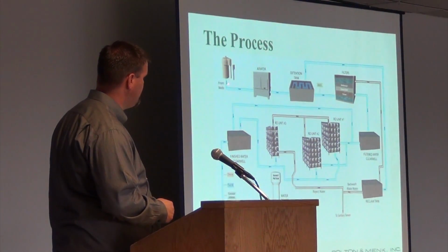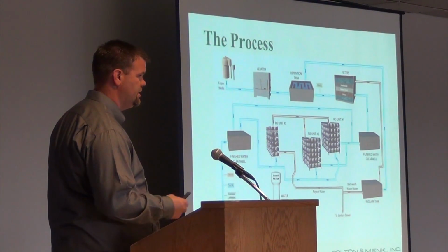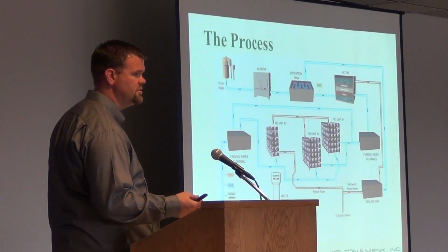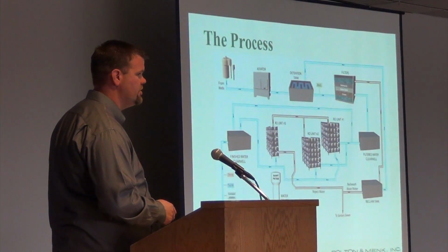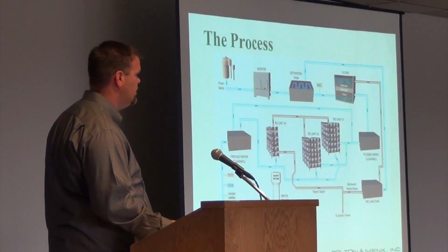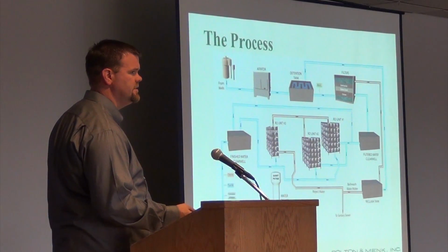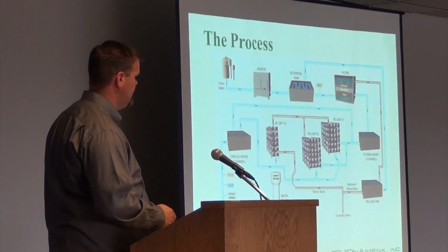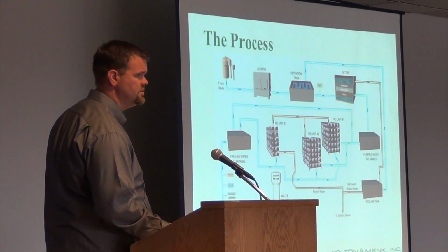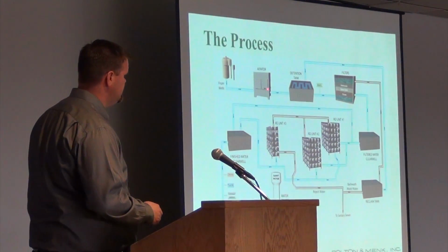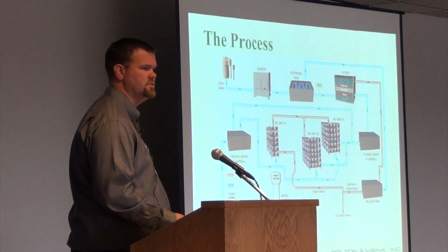But those wells pump up, it goes through an aerator to oxidize the iron, basically start to form iron particles that they can filter out. It goes through a detention tank to allow time for that reaction to occur. And then at the end of that tank, they add potassium permanganate, which is another strong oxidant to help oxidize the manganese. And then it goes through gravity, green sand, and anthracite filters. These three processes up top here are basically pre-treatment for the reverse osmosis system.